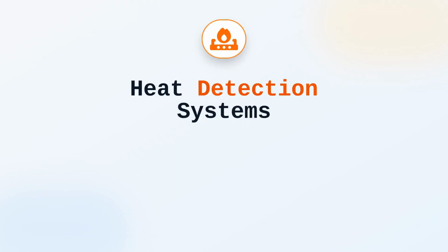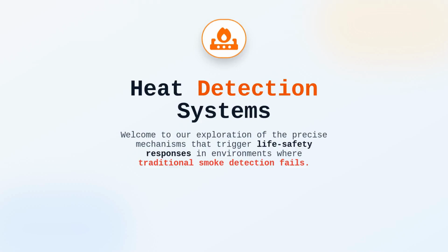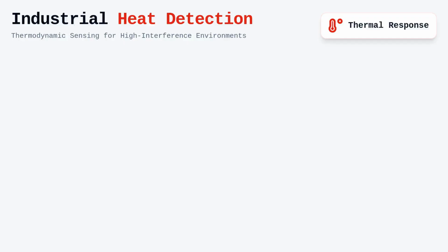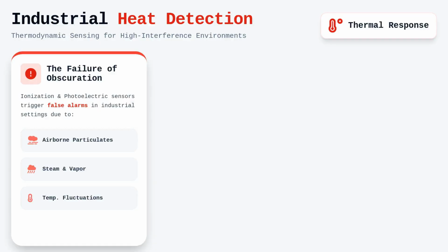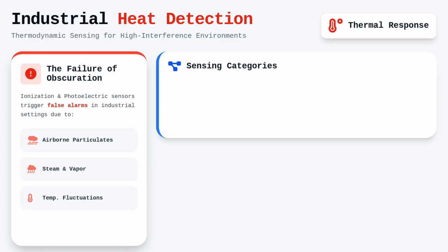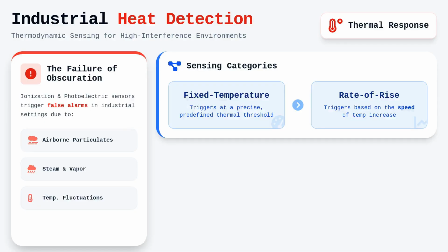Welcome to our exploration of heat detection systems, where we will examine the precise mechanisms that trigger life safety responses in environments where traditional smoke detection fails. In industrial or manufacturing settings, the presence of airborne particulates, steam, or extreme temperature fluctuations often renders ionization and photoelectric smoke sensors ineffective due to frequent false alarms. Heat detection serves as the primary alternative, functioning on the fundamental principles of thermodynamics rather than obscuration. These systems are categorized primarily by their thermal response characteristics, specifically fixed temperature operation and rate of rise detection.